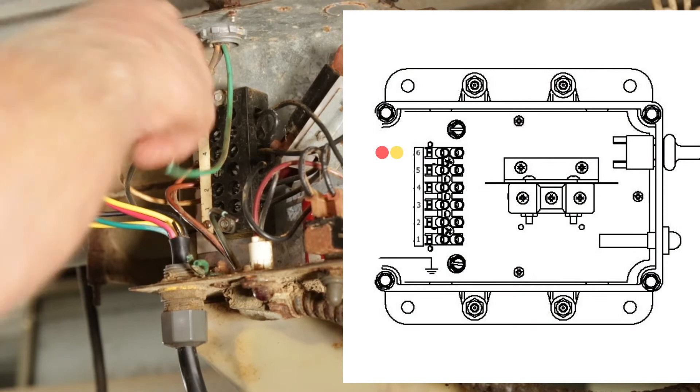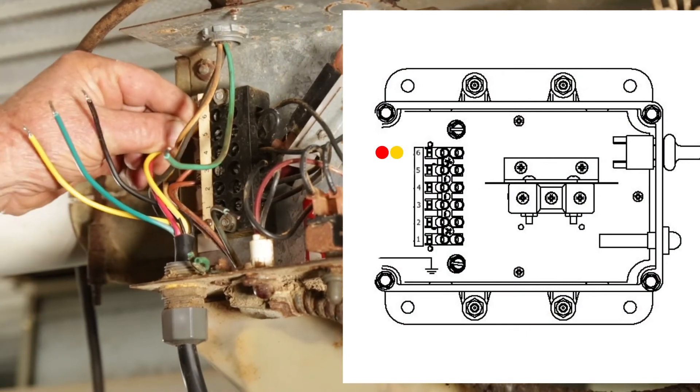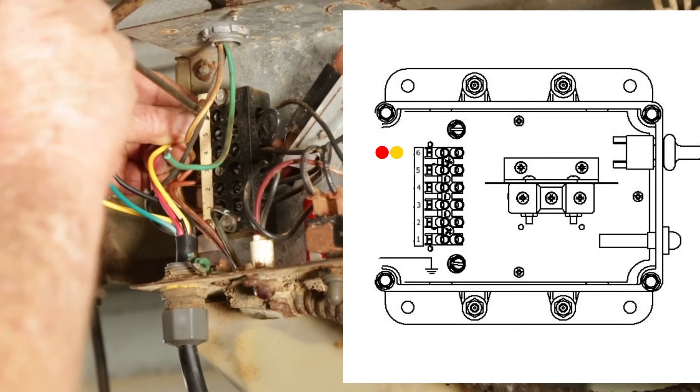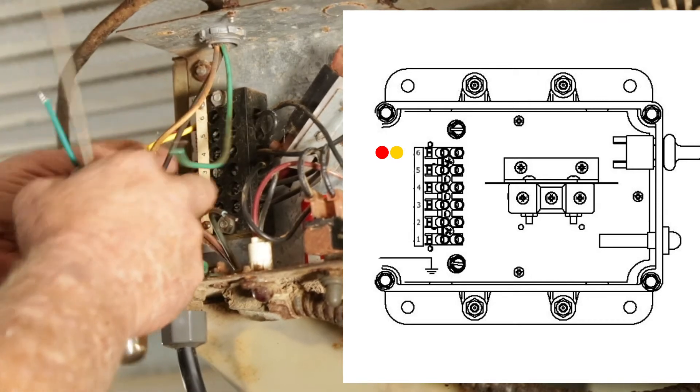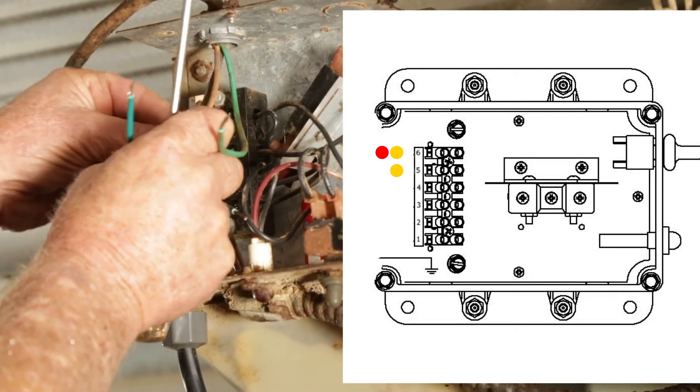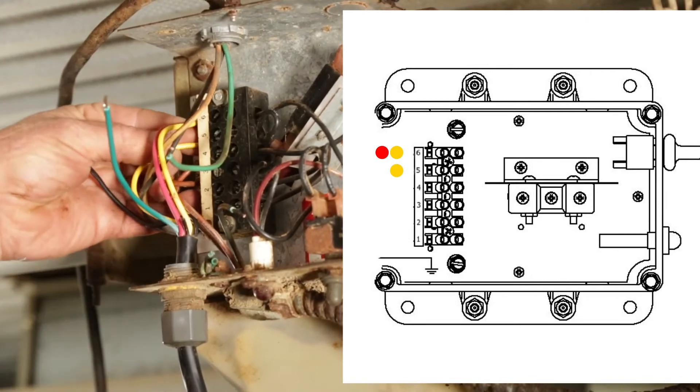Conjoin the red wire with one of the two yellow wires from the HS820 and connect them to the number 6 slot in the Chore-Time terminal. Then connect the second yellow wire from the HS820 to the number 5 slot on the Chore-Time terminal.